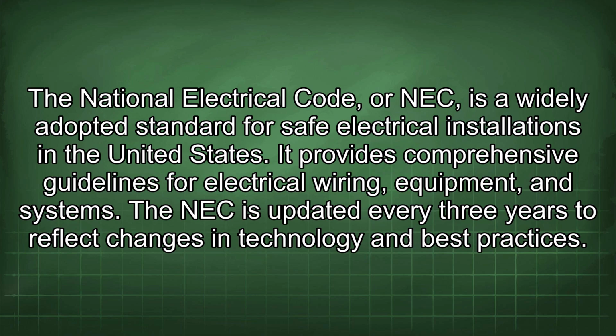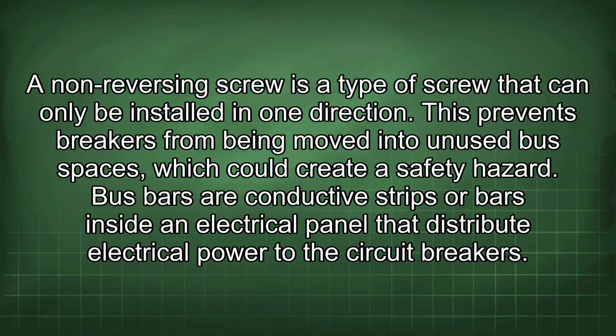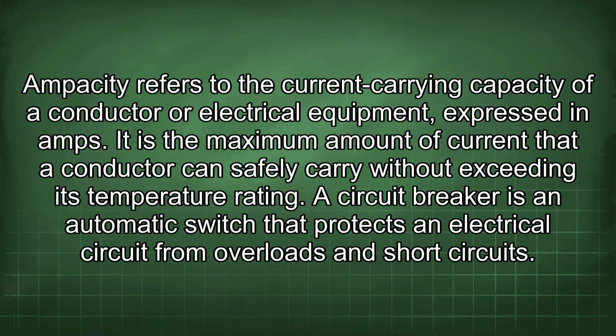The NEC is updated every 3 years to reflect changes in technology and best practices. A non-reversing screw is a type of screw that can only be installed in one direction. This prevents breakers from being moved into unused bus spaces, which could create a safety hazard. Bus bars are conductive strips or bars inside an electrical panel that distributes electrical power to the circuit breakers. Ampacity refers to the current carrying capacity of a conductor or electrical equipment, expressed in amps. It is the maximum amount of current that a conductor can safely carry without exceeding its temperature rating.